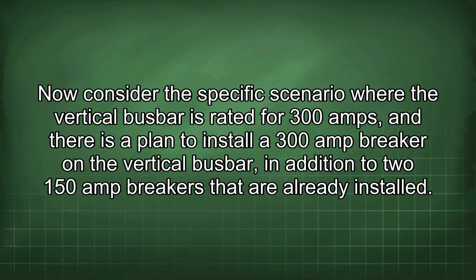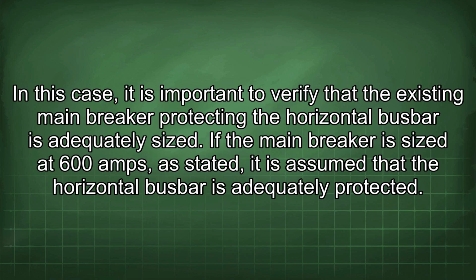Now consider the specific scenario where the vertical busbar is rated for 300 amps, and there is a plan to install a 300 amp breaker on the vertical busbar, in addition to two 150 amp breakers that are already installed. In this case, it is important to verify that the existing main breaker protecting the horizontal busbar is adequately sized. If the main breaker is sized at 600 amps, as stated, it is assumed that the horizontal busbar is adequately protected.